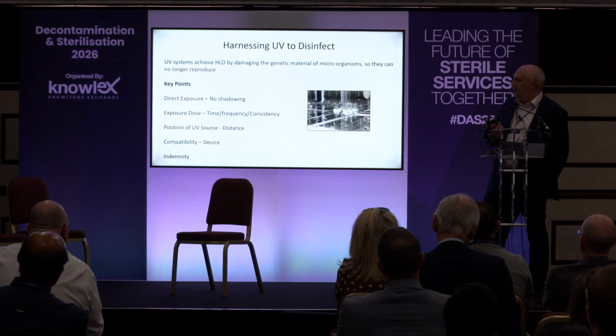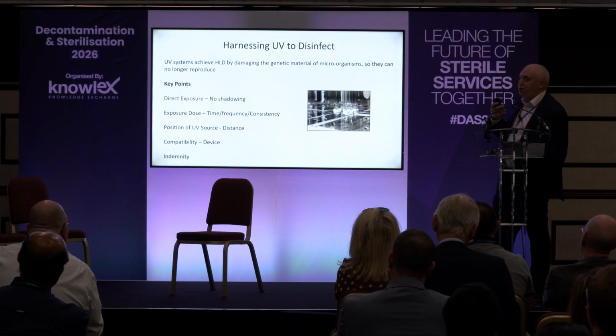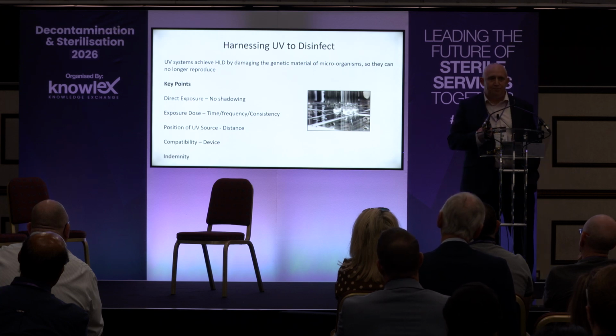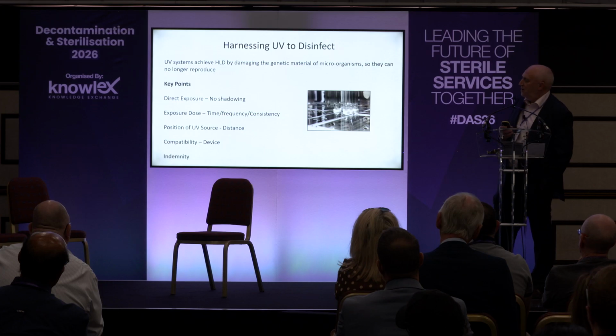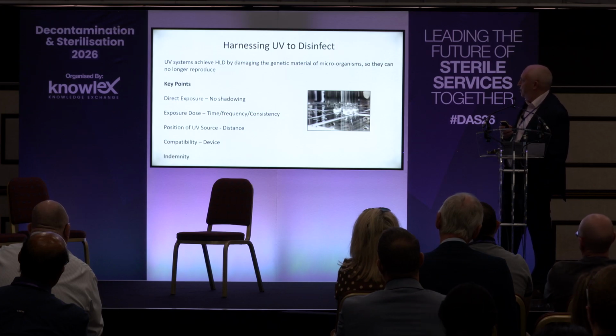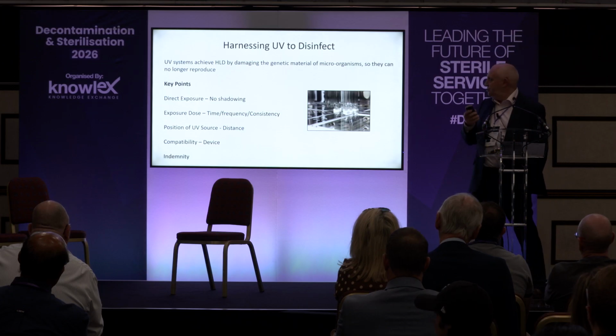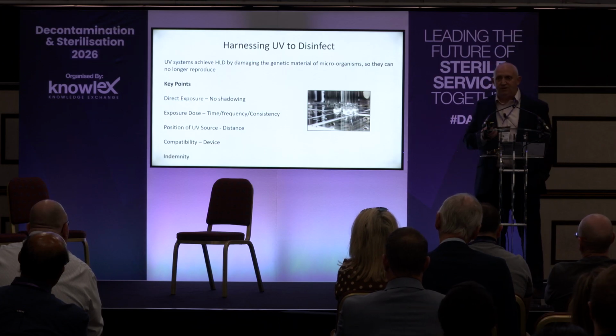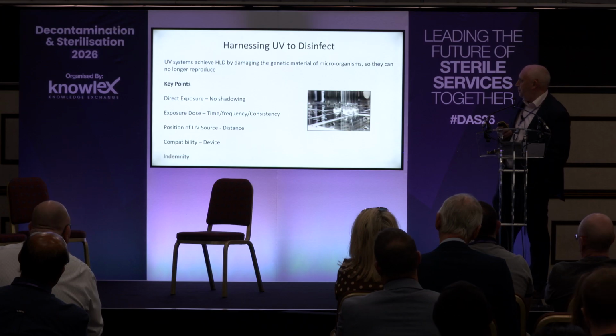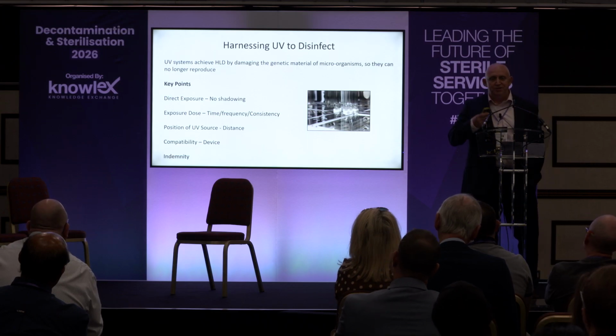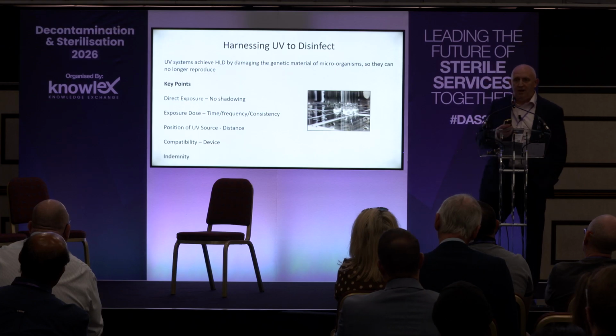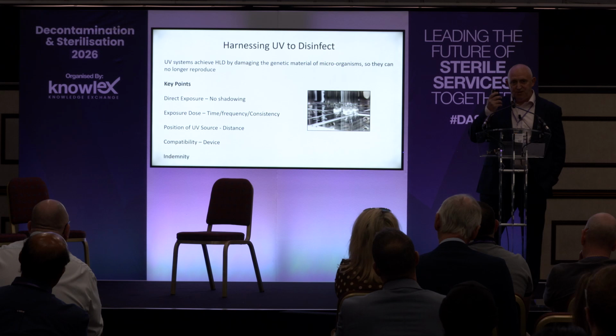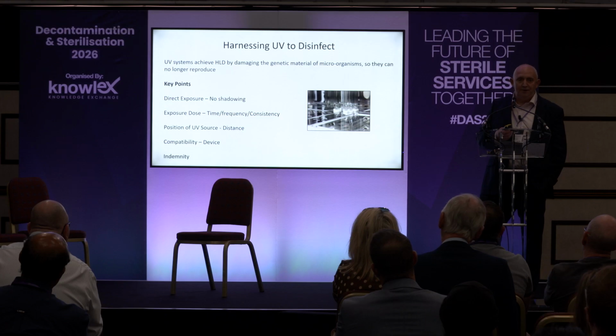We have to make sure we have the direct exposure. And the exposure dose is essential. That exposure dose will be set up during type testing, and we touched upon the importance of type testing a little bit earlier. That dose must be consistent, so the time must be consistent, the frequency of that dose must be consistent as well. The position of the UV source, the distance from the lamps is highly important as well. And that must hold that device in the same position on each occasion. If the bracket starts to wear and it's half an inch lower, you need to let the manufacturer know.